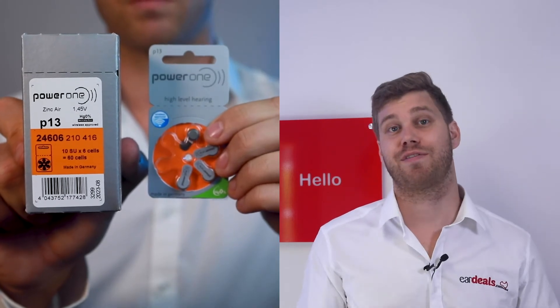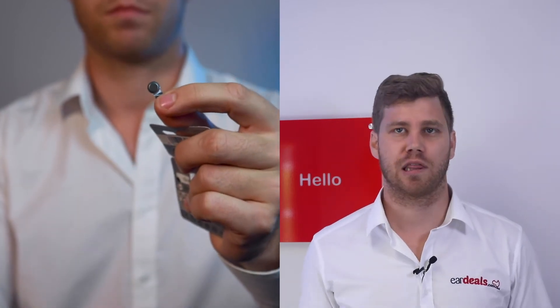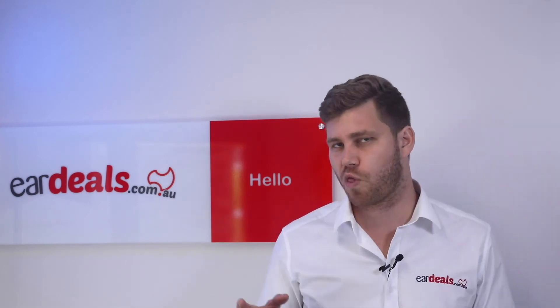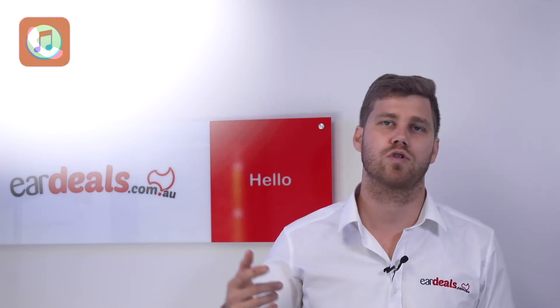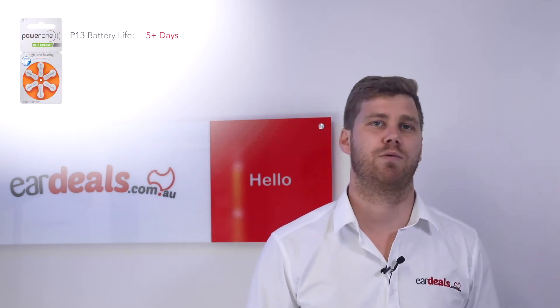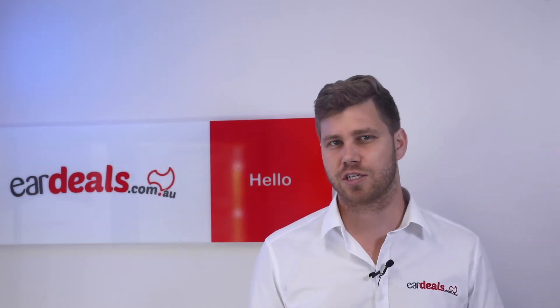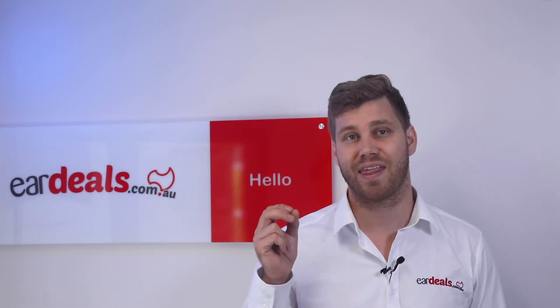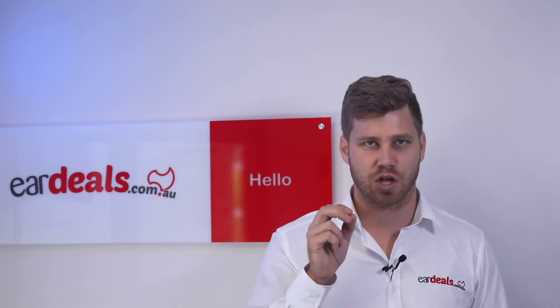The size 13T replaceable battery option on the ReSound One range is the largest replaceable battery available within the range, meaning big power for those with big hearing losses and longer battery life. However, it does come down to how much you're using the device for things like streaming phone calls, music, podcasts, or YouTube videos. Typically speaking, a size 13 battery will last anywhere from five plus days worth of charge. The device is larger because of that size 13 battery and also because of the T in the name — the size 13T.